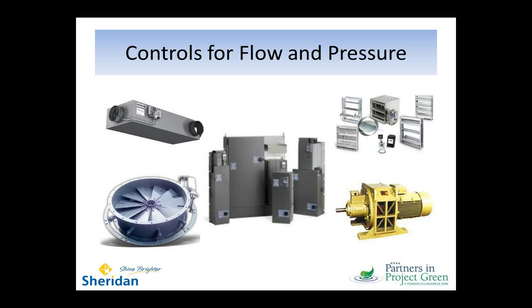In the middle are variable speed drives, which are adjusting motor speed to suit what's going on with the application. We'll talk about that a fair bit. At the top right, you see a number of output dampers. So these are controlling airflow on the outlet side. And at the bottom, what you see is a magnetic clutch, or essentially a device that's taking the shaft energy of the motor and providing some variability in how that power is coupled to the load at the other end of the shaft.